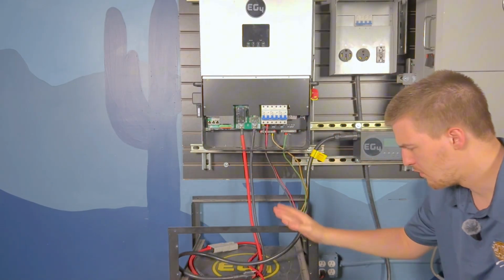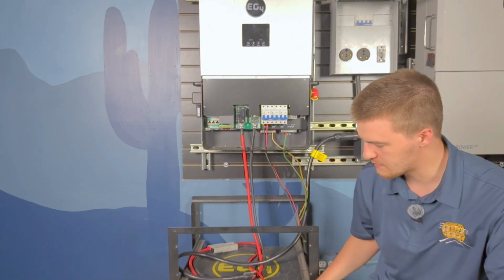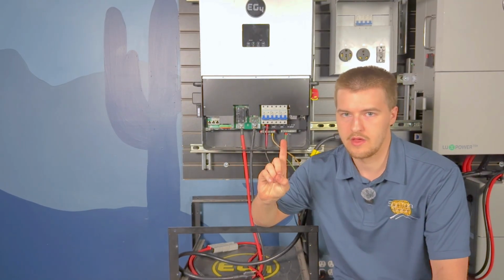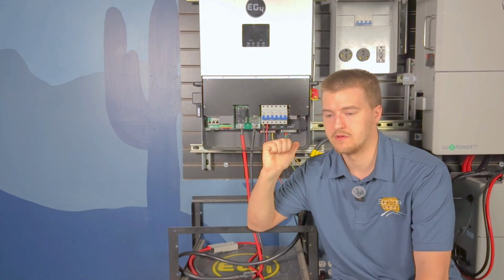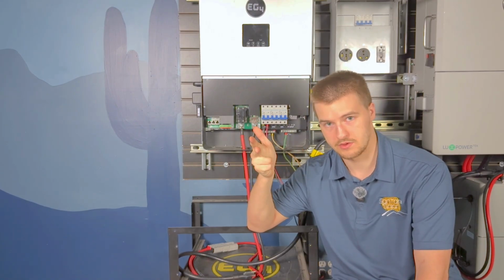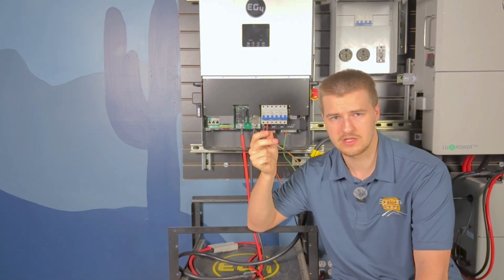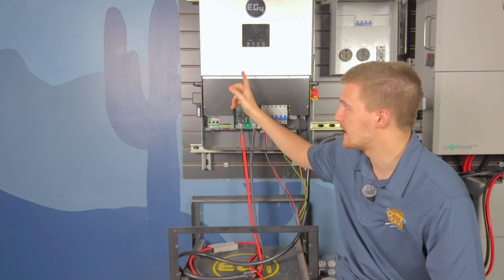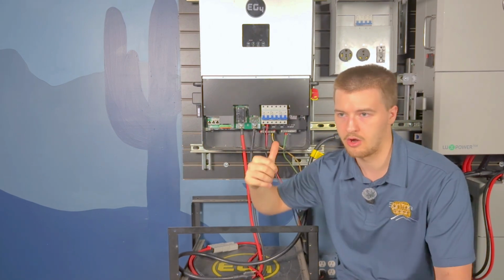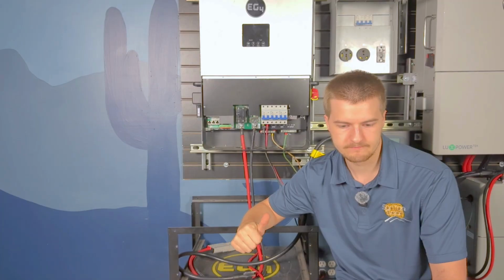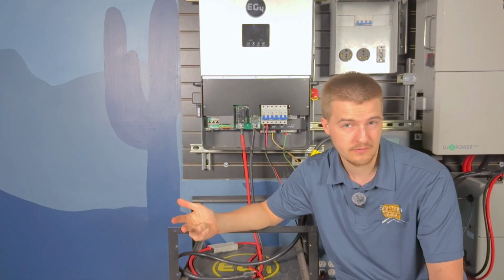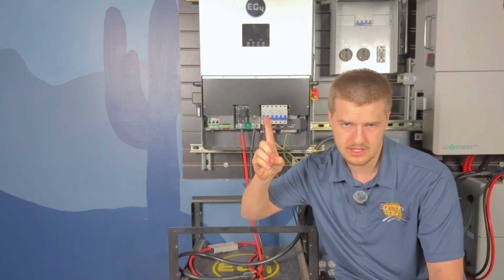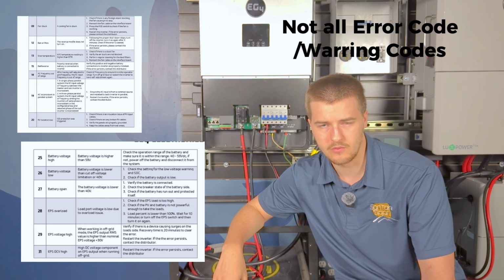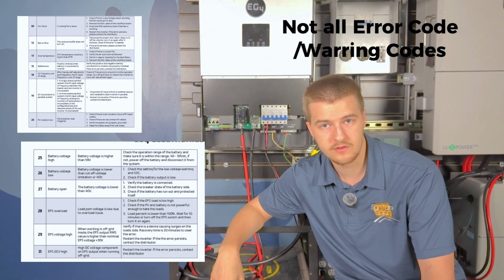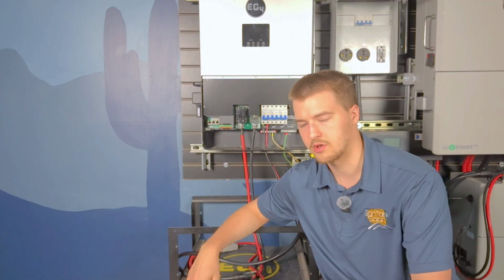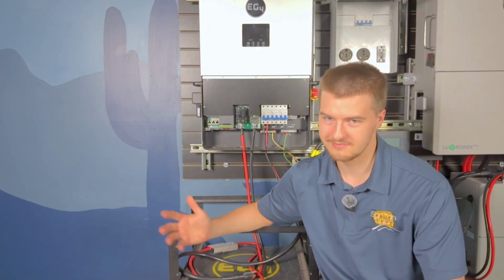When we're connecting our batteries, there are a couple things to keep in mind: our communication cable, our parallel cable, and our dip switches. Those are the three main important parts, because if they're not connected properly, we'll get an error on the inverter saying the battery's open, lost connection, or communication failure with the battery. I can put the error codes and warning codes on screen and what to do when you get them, or you can check the documentation.